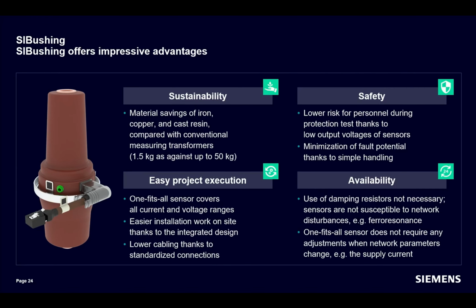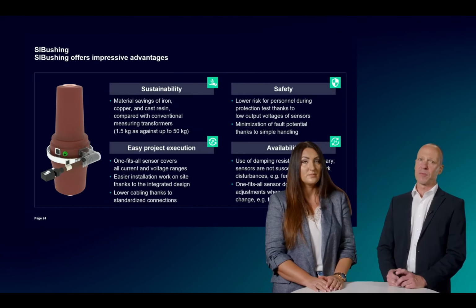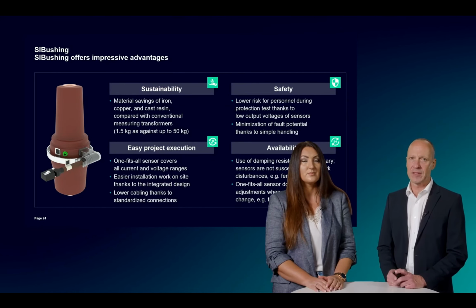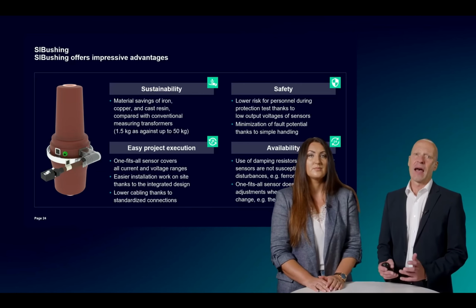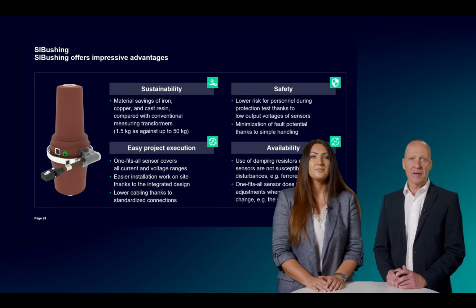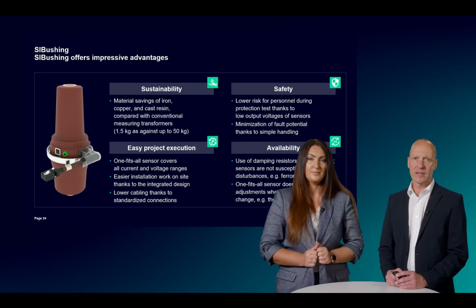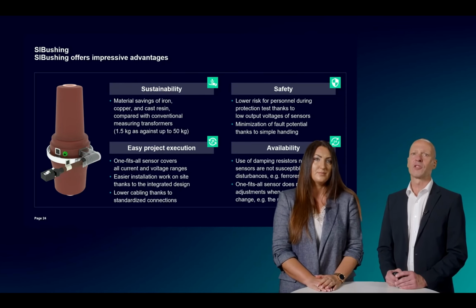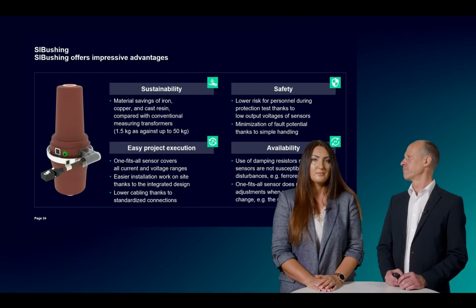Further simplification of the project execution is given due to the one-fits-all design. We have only one SIBushing for all voltage and current ratings in the factory stock. A later upgrade of grid parameters is also possible without adjusting or replacing any components. And last but not least, also safety on site during commissioning and testing is higher due to low voltage outputs and no need of cabling or installing of instrument transformers around or on the cable.